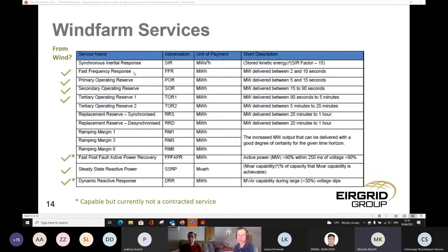The fast frequency response should occur very fast. For example, if you go from a 0.5 hertz per second RoCoF measurement threshold to 1 hertz per second, if the measurement takes time, and sending the signal to the wind turbine takes more than 300 milliseconds, that would be too late, and we would have a deeper frequency nadir, in my opinion. I was told that 300 milliseconds would be good enough for sending the signal, but I'm not sure about this data.